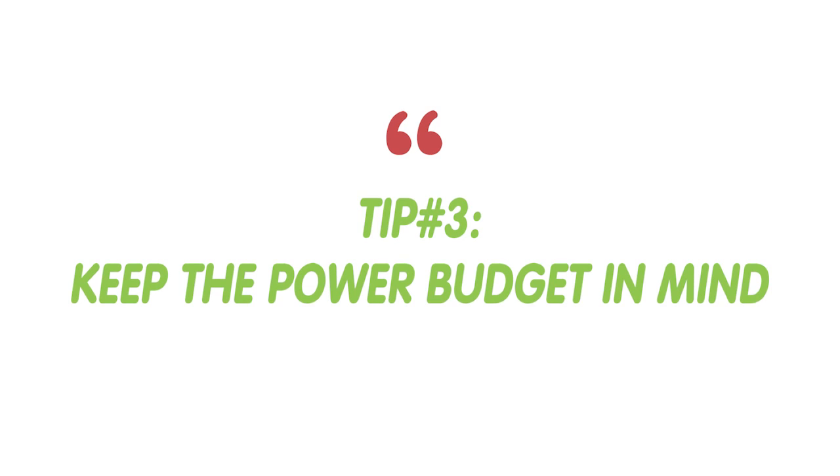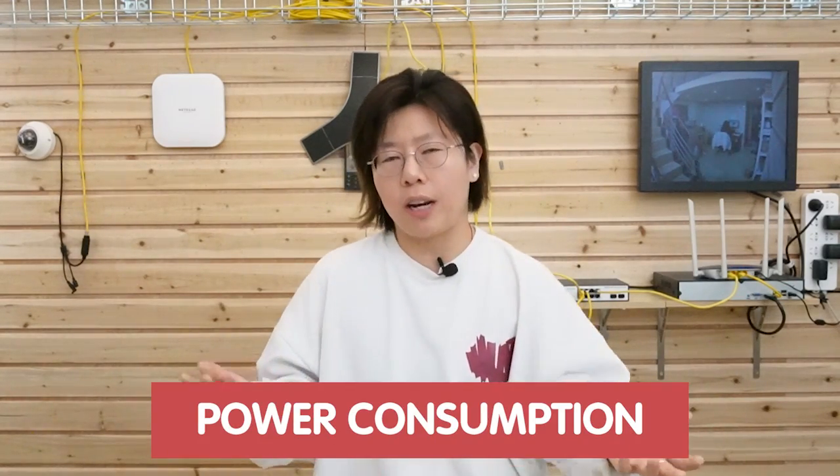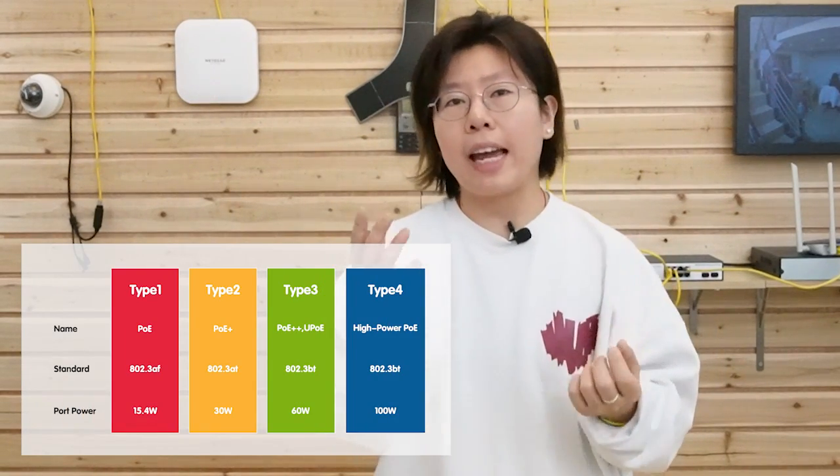Tip number three: keep the power budget in mind, because people tend to forget about it. If you have a BT-standard IP camera and plug it into an AT-standard PoE switch, it's not going to work because of the power consumption and power loss. The PoE system has AF, AT, and BT standards. Make sure you match the PoE standard between your switch and your devices.